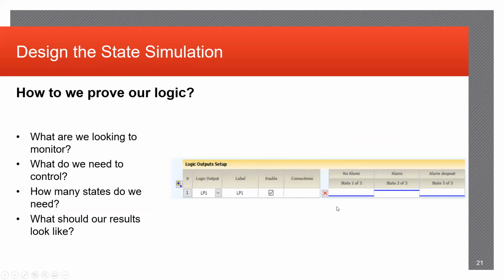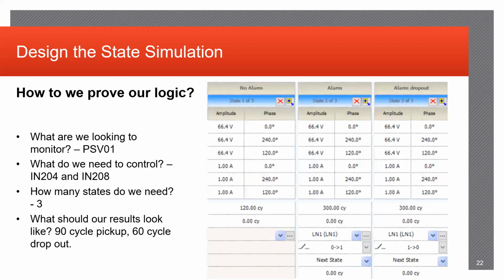allowing the test set to not only initiate the correct output contact when need be, but also ensure the relay doesn't pick up when it doesn't need to. Proven logic, let's see here.